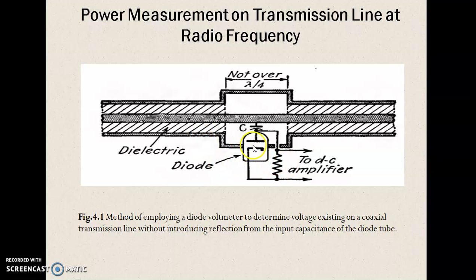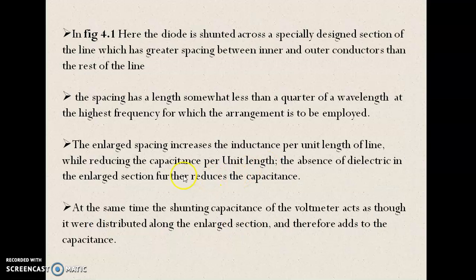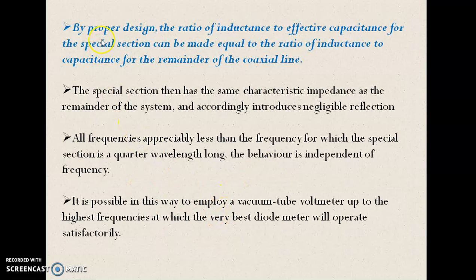By proper design, we can make sure that the ratio of inductance to capacitance at this special section is equal to the ratio of inductance to capacitance at the remaining section of the transmission line. If this ratio is the same, then we can say that the special section has the same characteristic impedance as the remaining section of the transmission line. That will help in introducing a negligible amount of reflection in the system, which was our purpose in the first place when designing this special section.